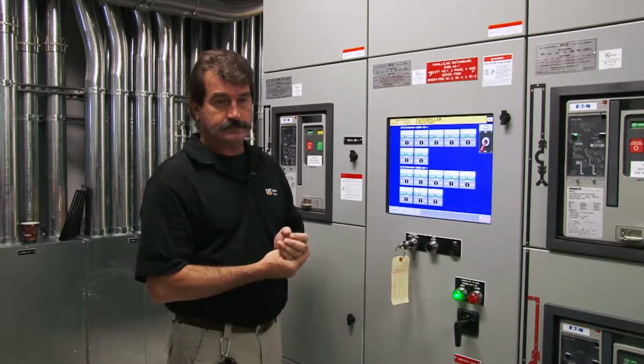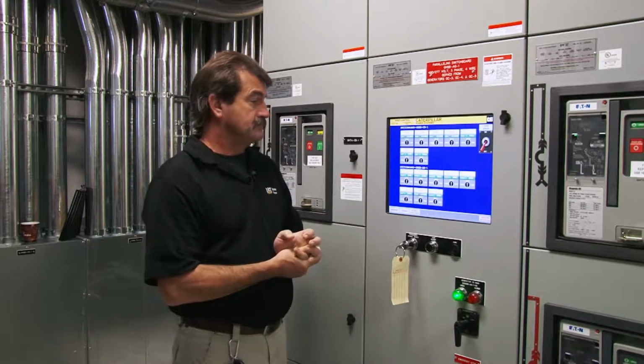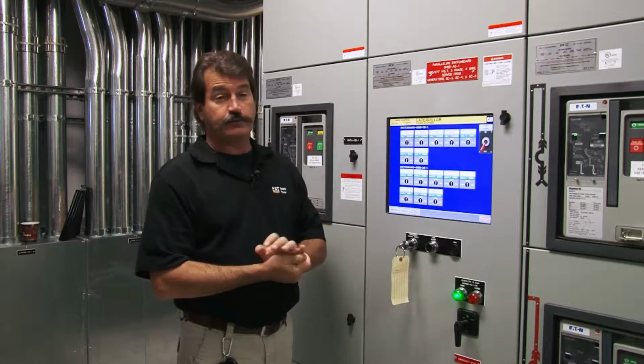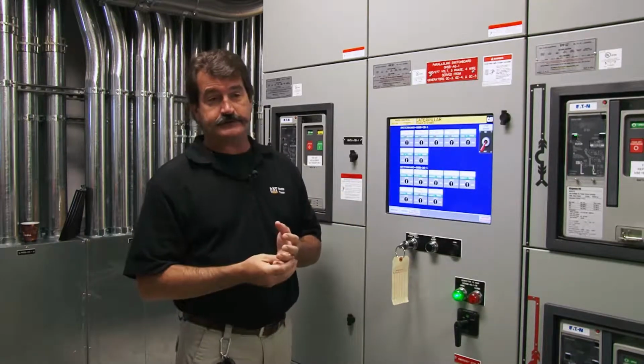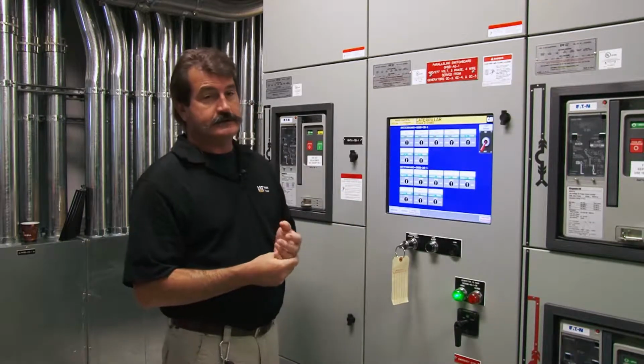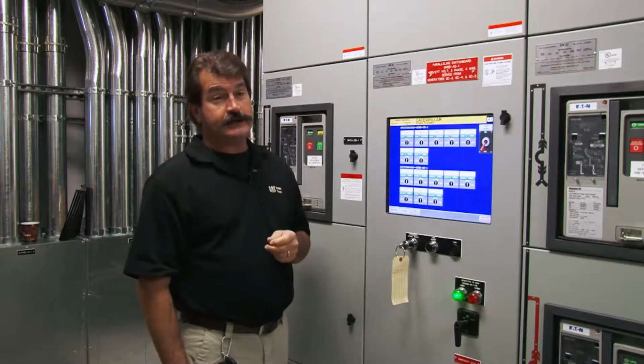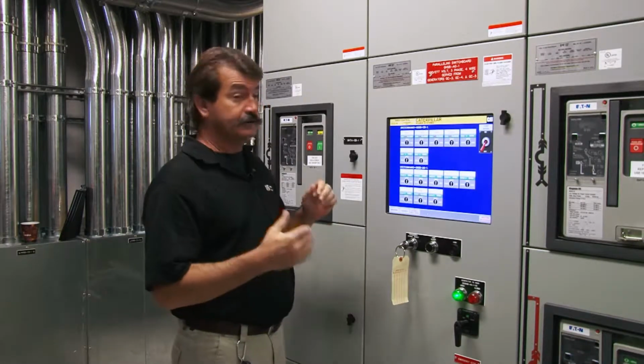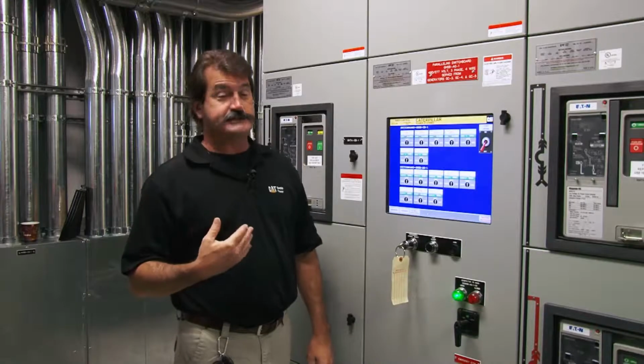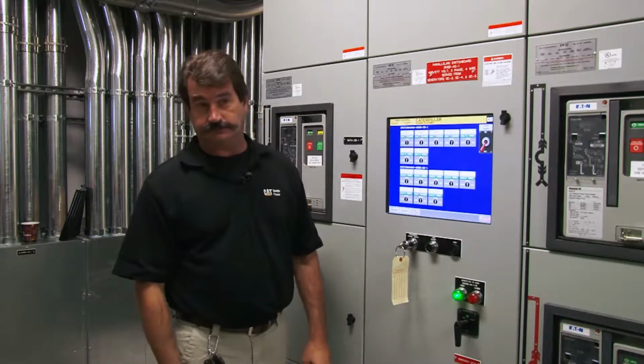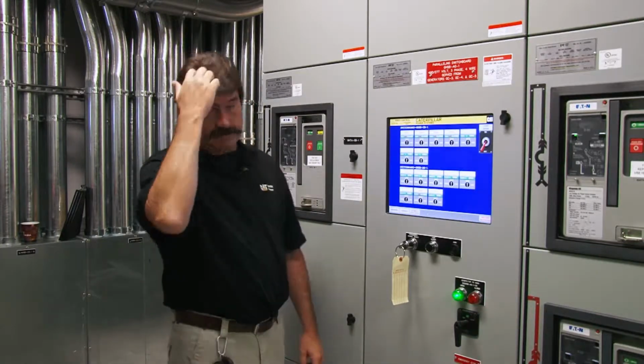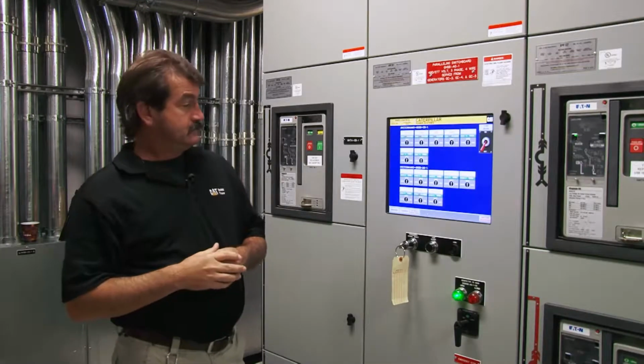Say 5 never cranks. Say you had a problem with 5. Does that breaker close in? No, the breaker will not close because you do not have load sense on. Okay. And can you go in and manually transfer it? Yes, you can. It will not hold that breaker open. It just will not try to close that breaker. Okay. So how can I change that?